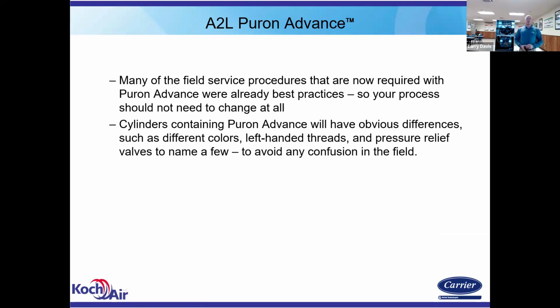Let's see. Many of the field service procedures that are required with Puron Advance were already best practice. We already talked about that. Really, the only thing that's going to change about the process is those corners we were kind of cutting before. Those little steps we were kind of skipping, thinking we could get by with it, can't get by with it anymore. The cylinders for Puron Advance are going to be a different color. They'll have the red band around them, left-handed threads where you hook your hose. And instead of a rupture disc, it's going to have a pressure relief valve that reseals. So it's a spring-loaded pressure relief valve versus a one-time plug. Okay.